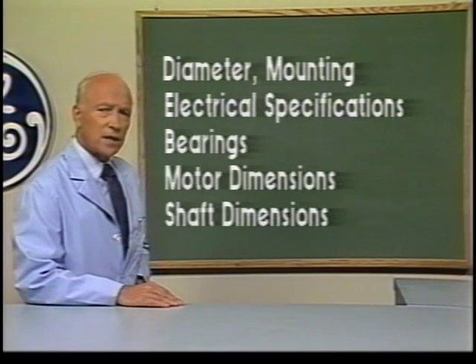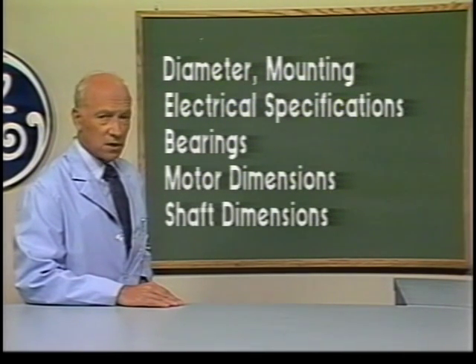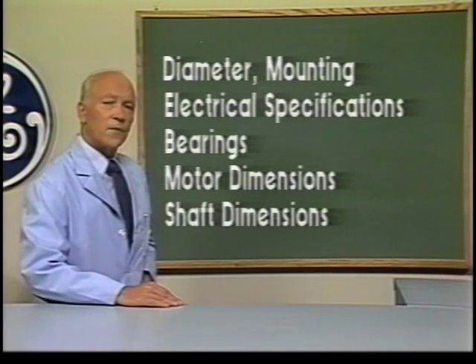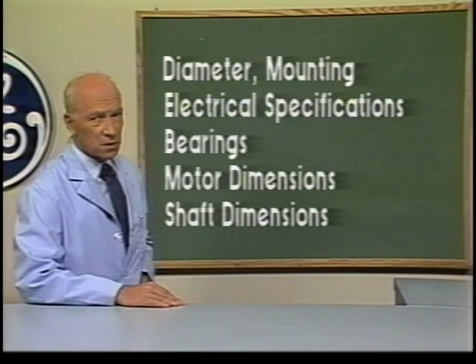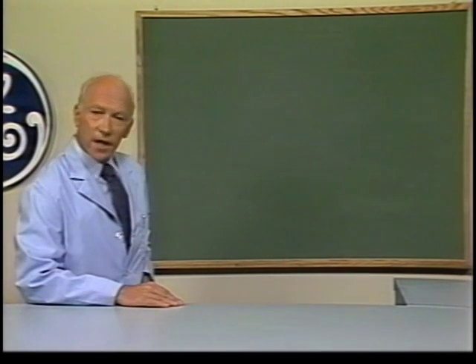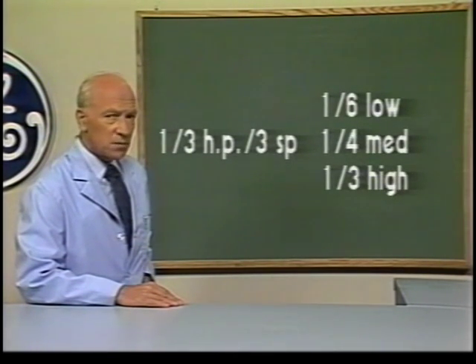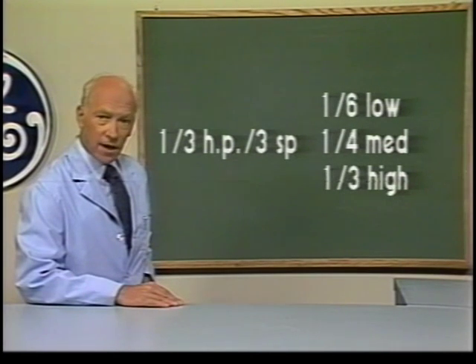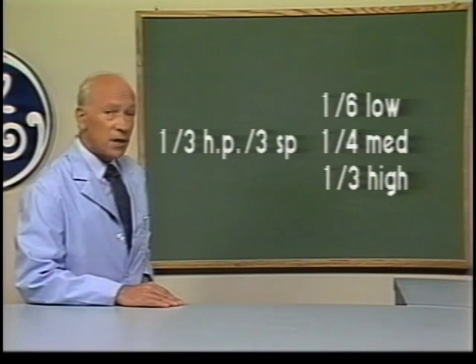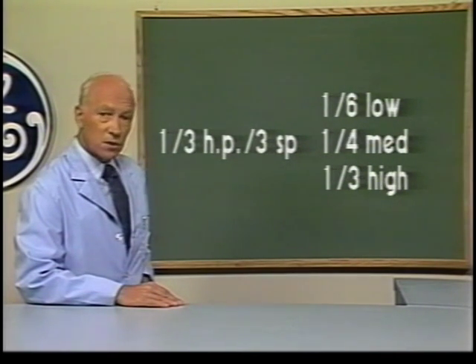To review the checklist: diameter, mounting, electrical specifications, bearings, motor dimensions, and shaft dimensions. The chances are good that you will find a good replacement. Even if you can't find an exact duplicate, many customers will be more than satisfied with a legitimate substitution. For example, if you need to replace a one-third horsepower single-speed motor but don't have one in stock, look at your multiple-speed motors. A one-third horsepower three-speed motor typically has one-sixth horsepower at low speed, one-quarter at medium, and one-third at high. By taping the leads for the lower two speeds, you now have the one-third horsepower single-speed motor you need.